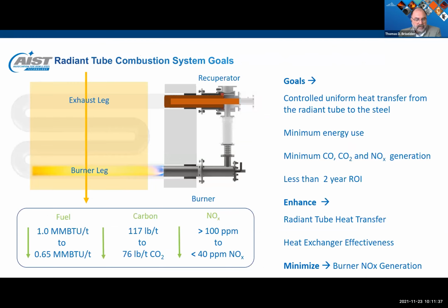So let's zero in on the radiant tube itself. We want uniform heat transfer from the tube to the steel. Minimum energy use, CO, CO2, and NOx generation. Preferably less than a 2-year return on investment or payback. In a report generated by the Department of Energy, they identified the theoretical practical reduction of energy as going from 1 million BTUs per ton to 0.65. This corresponds to a CO2 reduction per ton from 117 to 76 pounds. And then the South Coast Air Quality Management District, which seems to be the most stringent in the US, is targeting less than 40 ppm for industrial applications in industrial heating processes.